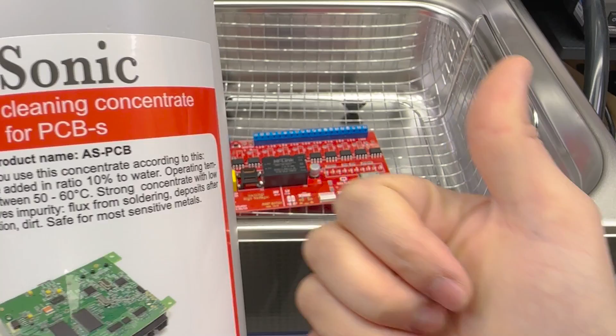Second precaution is to not run your ultrasonic cleaner with flammable liquids. For example, you might be tempted to put isopropyl alcohol or other flammable cleaning liquids inside your ultrasonic cleaner. And when heated up, those highly flammable liquids are very dangerous and very likely to catch fire. Can you imagine having a huge tub filled with flammable liquid that catches fire inside your small lab or home? That would be disastrous. All you need is a modern non-flammable cleaning solution designed specifically for this purpose, and you'll be running your ultrasonic cleaner in a very safe way.